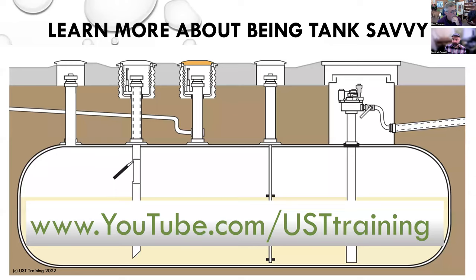What's the next question. A couple of smaller points down here below. Ellen Mink asks, a brine liquid sensor can go into an alarm if level rises or drops, correct? That is correct. If it's dropping, then the outer chamber is probably leaking. If it's rising, maybe there's a hole inside the tank. So it's not so much about just dropping, it's a change in condition.